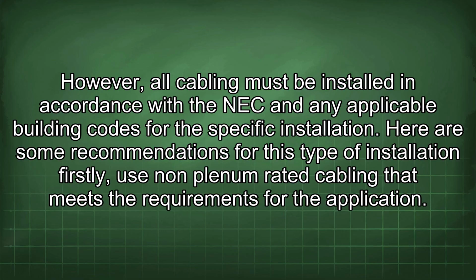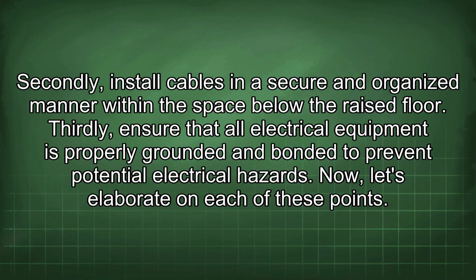Firstly, use non-plenum rated cabling that meets the requirements for the application. Secondly, install cables in a secure and organized manner within the space below the raised floor. Thirdly, ensure that all electrical equipment is properly grounded and bonded to prevent potential electrical hazards. Now let's elaborate on each of these points.